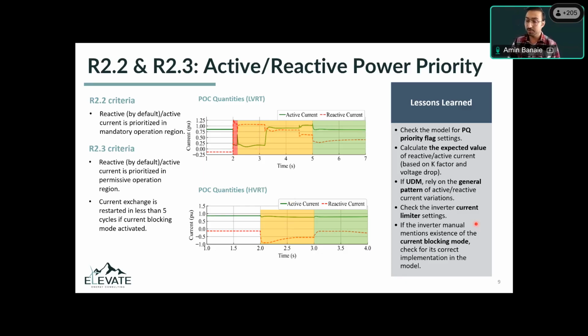So yeah, current limiter setting is also important, as I said, if that curtails reactive current. And also another factor is the current blocking mode. So make sure that that is implemented correctly in the model, and check the inverter manual and make sure that it matches what's in the field. If you see both active and reactive currents go to 0 here in this permissive operation region, that's an indication of activation of current blocking mode, and R2.3 wants that mode to be restarted within 5 cycles at most. So you want to be careful with that as well.